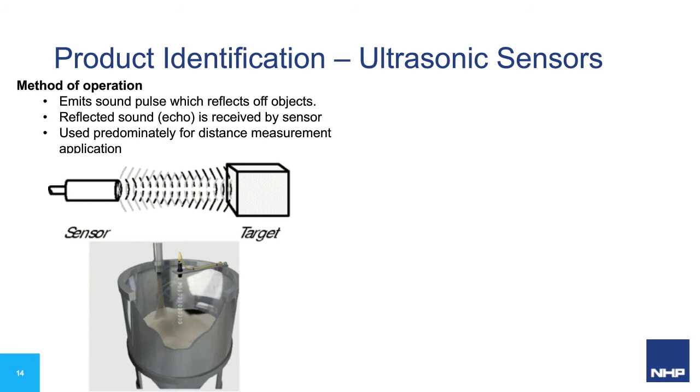Now, due to this operation, they can be used on multiple types of surfaces or materials, as mentioned before, provided they act as a solid when the sound waves hit them. So you wouldn't want to use this on acoustic foam or another surface that would significantly absorb or scatter the sound waves in directions other than the sensor face.